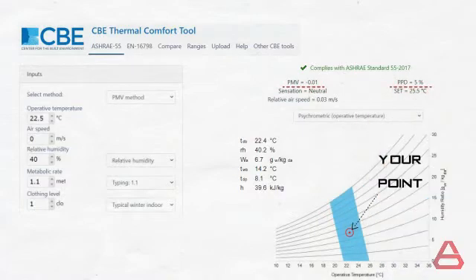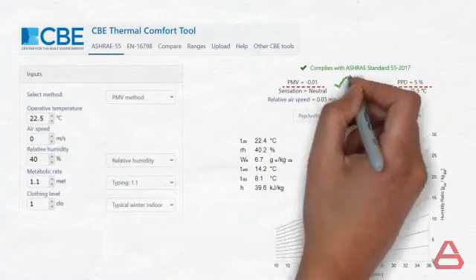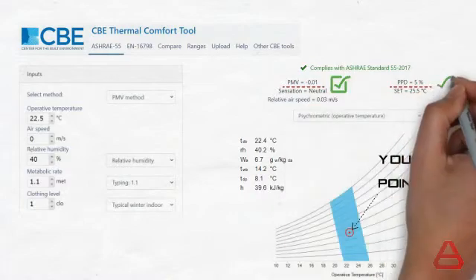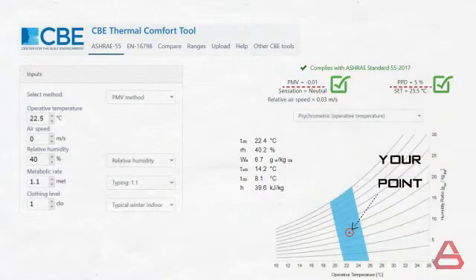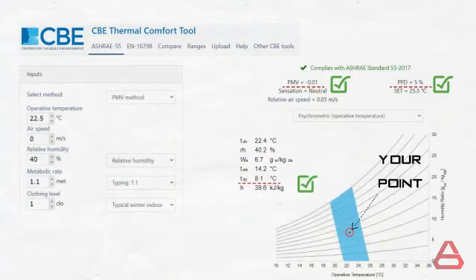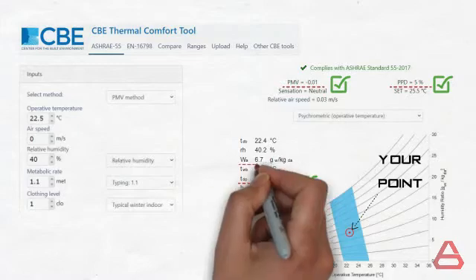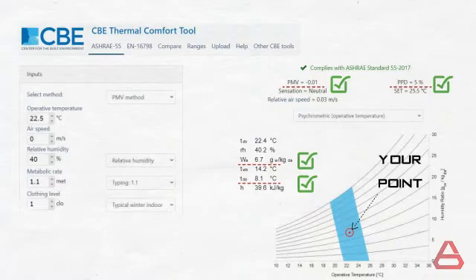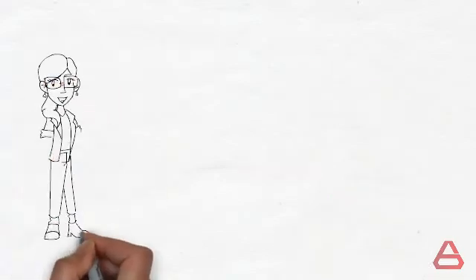In our case, the PMV turns out to be minus 0.01 and the PPD 5% which are excellent. The dew point temperature is 8.1 degrees Celsius and the humidity ratio is 6.7 grams of water per kilogram of dry air.